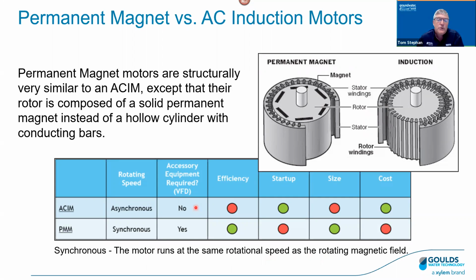Another key difference here is, do I need a VFD? So as most of you know, we don't need a VFD with the induction motor. However, we certainly can put one on that motor. With a permanent magnet motor, we have to have a VFD with that motor. So that's one key difference. And so there are some differences here as well. Let's just focus on one, and that's efficiency. The one key difference with that permanent magnet motor is also that it's very, very efficient compared to the induction motor. And frankly, that's why we're seeing more and more of these motors in the marketplace today. And I think we'll see more in the future as well. So let's get back to the induction motors.